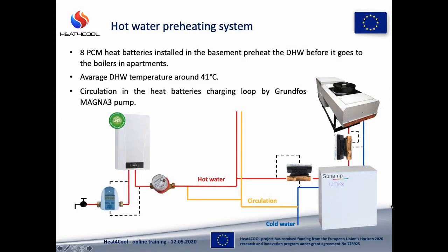In case of the domestic hot water system, there are also 2 circuits separated by the heat batteries in the basement. So heat batteries have the role of the heat exchanger. They are responsible for preheating of the cold water from the water mains, and the average temperature at the outlet of the heat batteries is around 41 degrees. From the heat batteries, the water runs to the apartments, to the boilers, where it is heated further in case the boiler set point is higher than the temperature provided from the heat batteries.